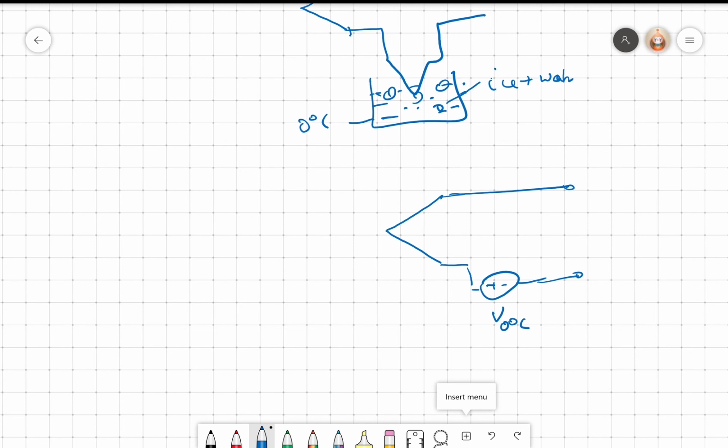We don't do it nowadays. We can generate this by using standard semiconductor voltage generation. So many modern thermocouples will come with inbuilt 0 degree compensation, so that you don't have to do anything on that front.